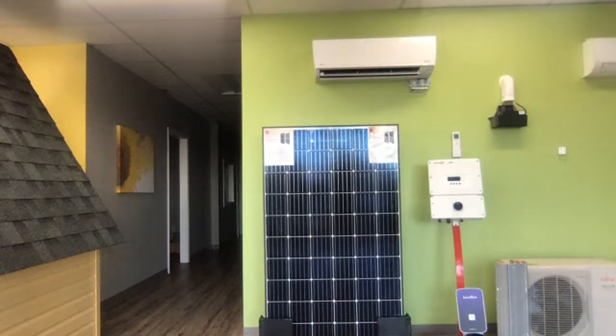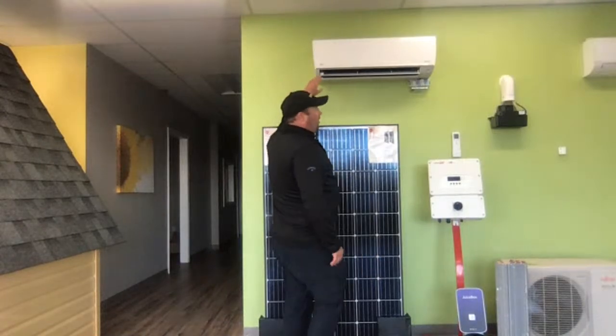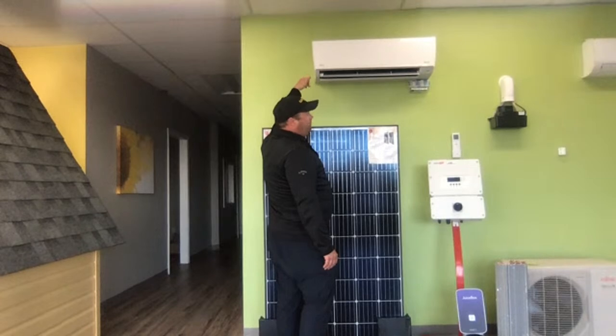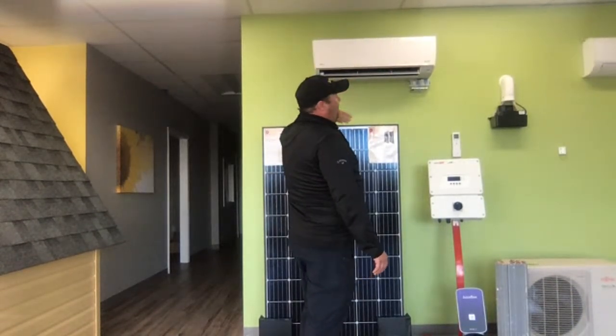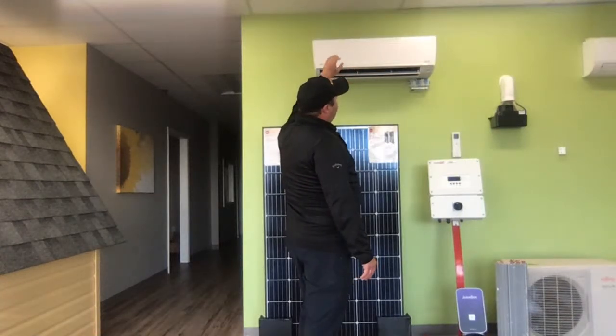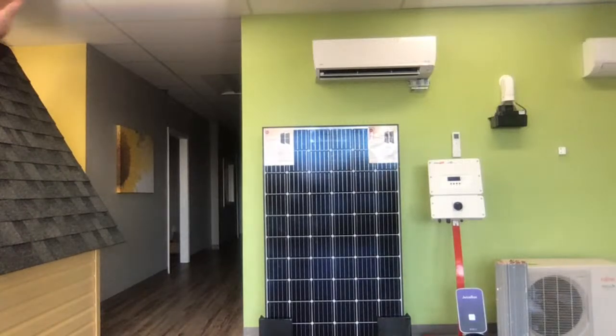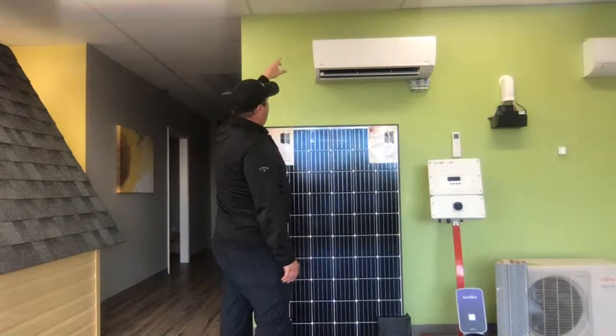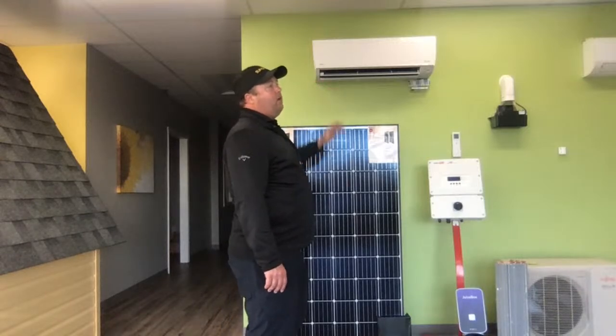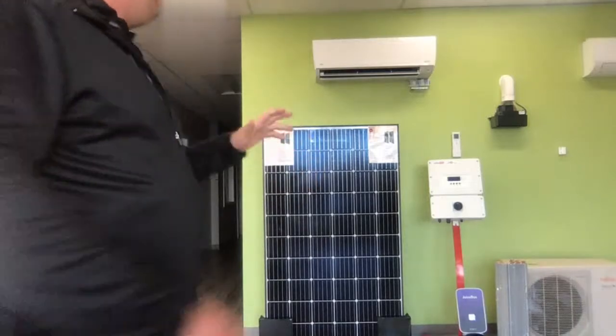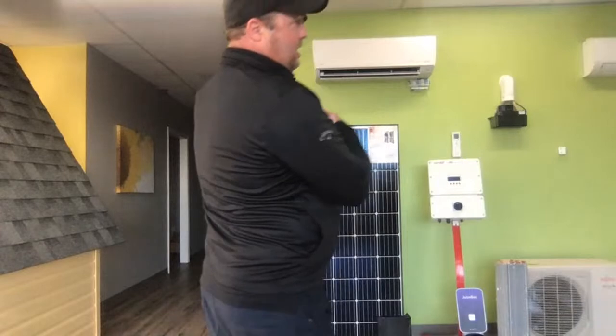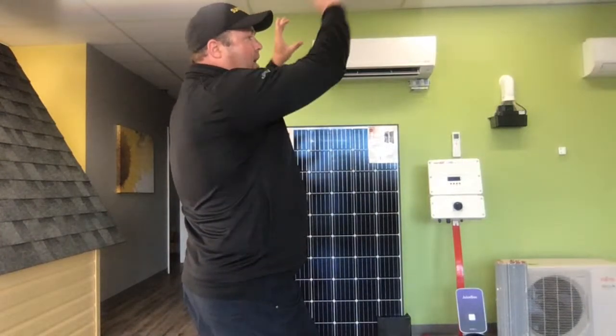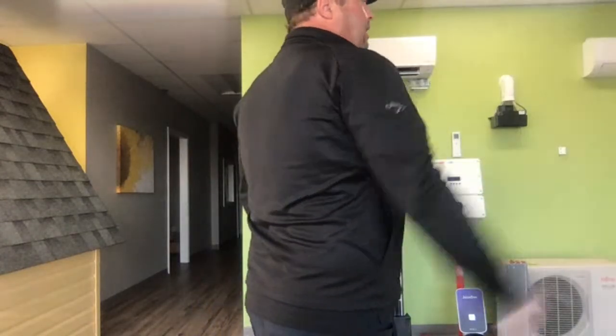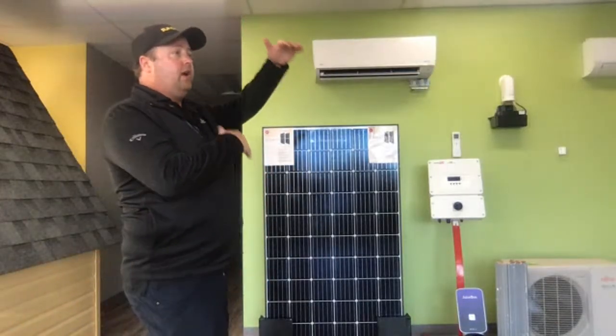How far from the ceiling does the unit have to be? That's a good question. Most heat pumps are anywhere between 11 and 12 inches top to bottom, and they breathe from the top. I've seen them go as low as 2 inches, but really you want 3 or 4 inches off the ceiling. So from the top of the ceiling down to the bottom of the unit, your minimum distance is around 15 inches. If you're trying to put it over a window, lots of times that can't happen—you need a high ceiling with a big 18-inch gap, because even over a window or door, you can't forget the frame around it. We can't go through that frame, we have to go above it. So if it sticks up 6 inches and you've got 20, I still can't go through it. It all depends on the house.